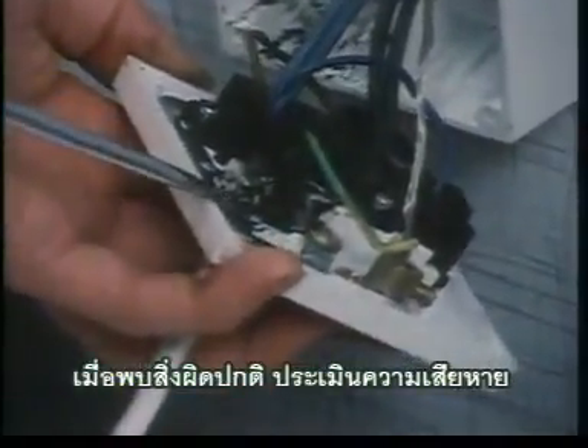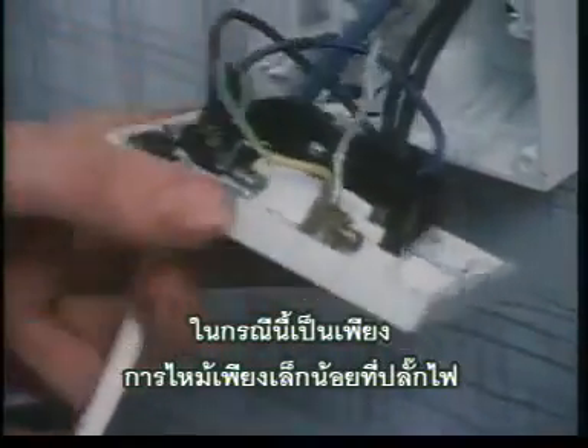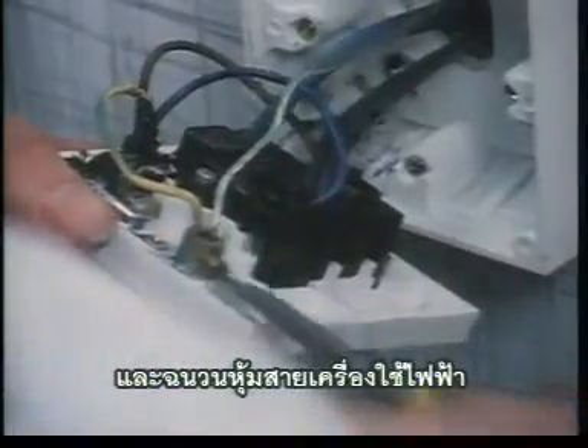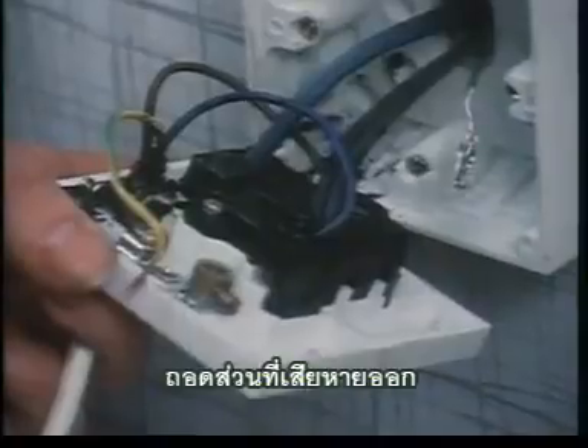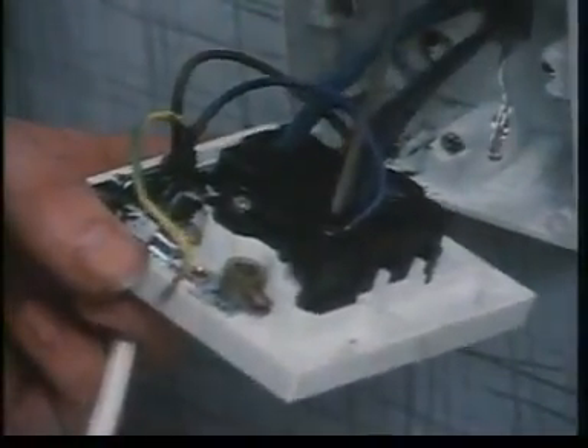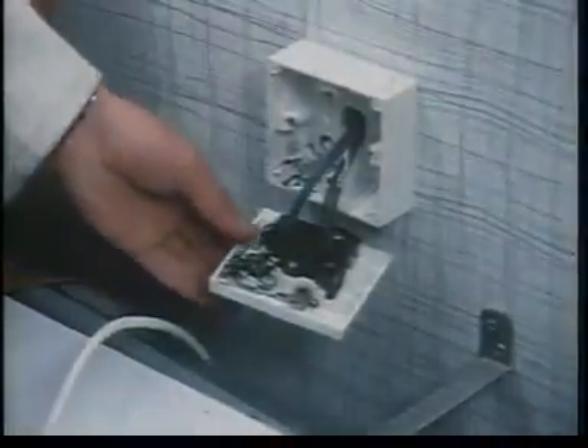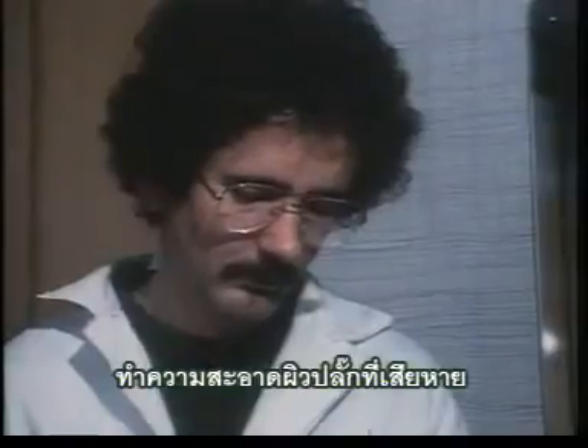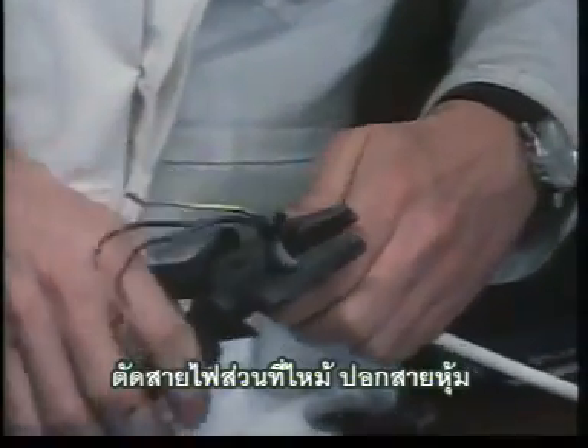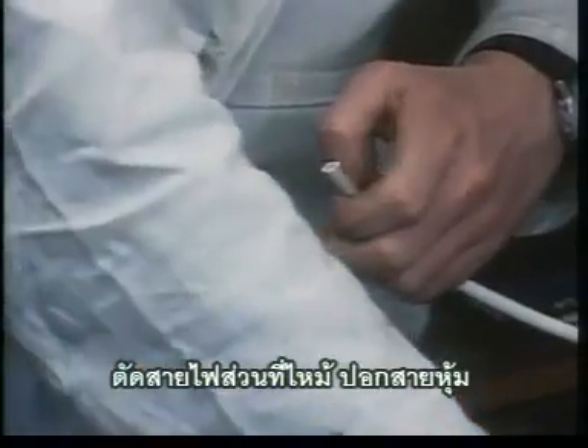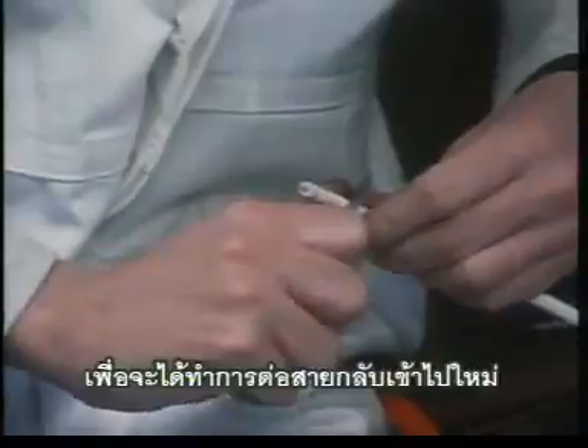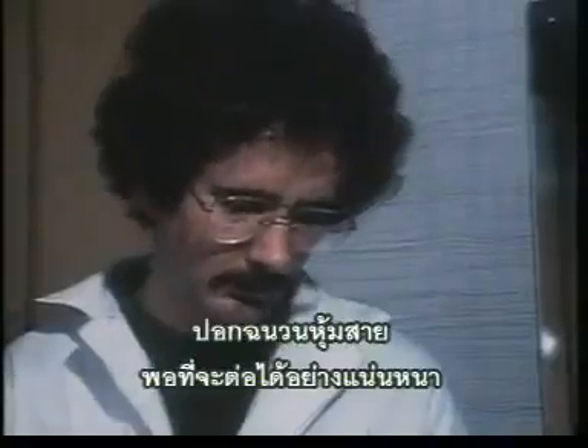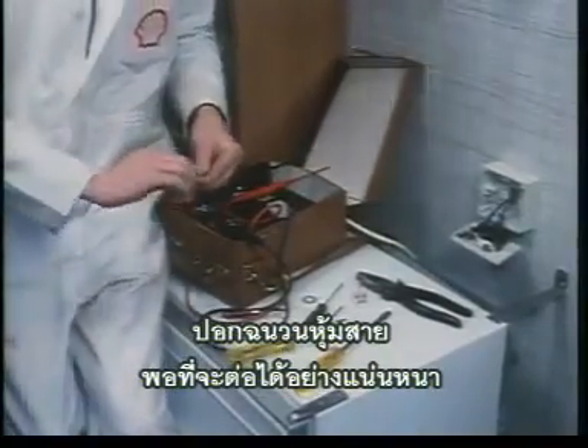When the fault is located, the damage must be evaluated. In this case, only a minor burn is found on the fitting, other than the damaged insulation on the conductor. Disconnect the damaged cable so that it may be removed. Clean the burned surface of the fitting. Cut off the damaged part of the cable and strip back the outer insulation, about 6 or 7 centimeters or 3 inches, to allow the cable to be reconnected. Then bare enough conductor to facilitate proper and secure electrical contact.